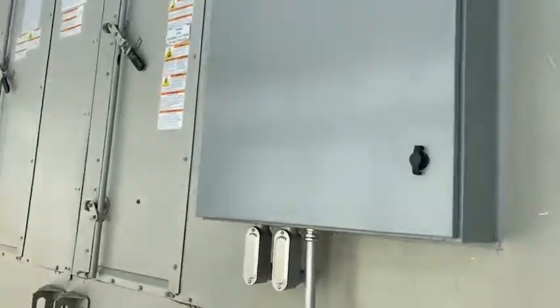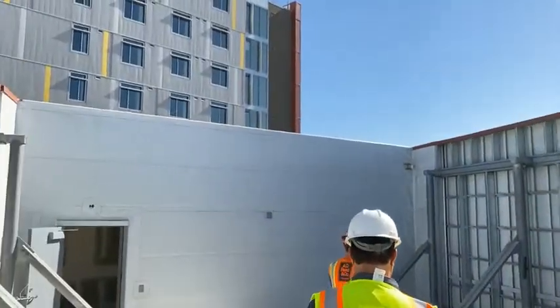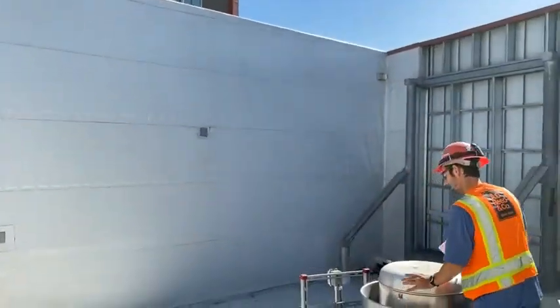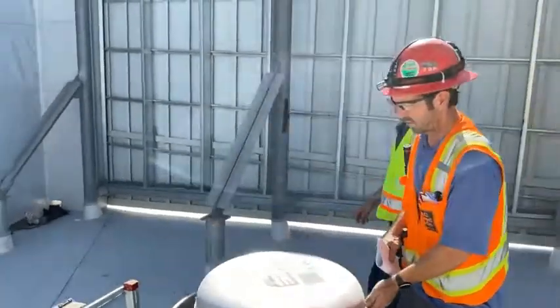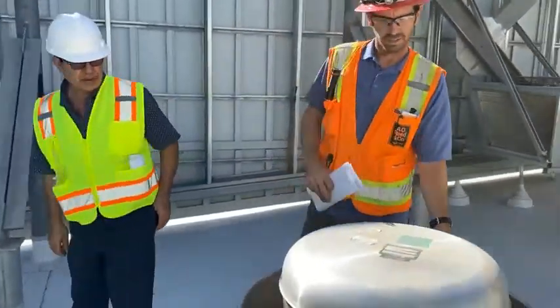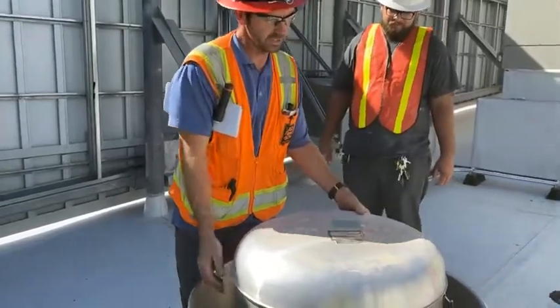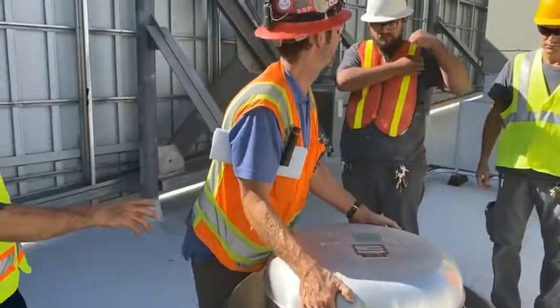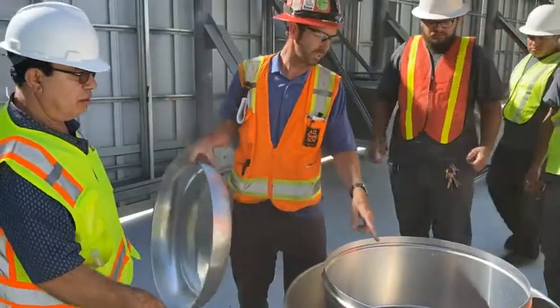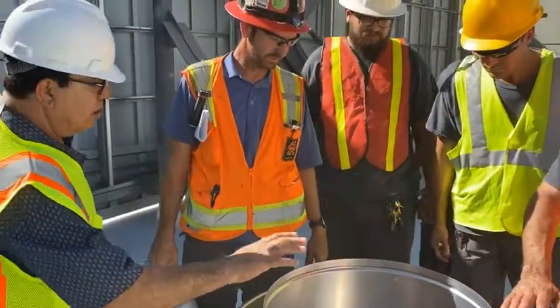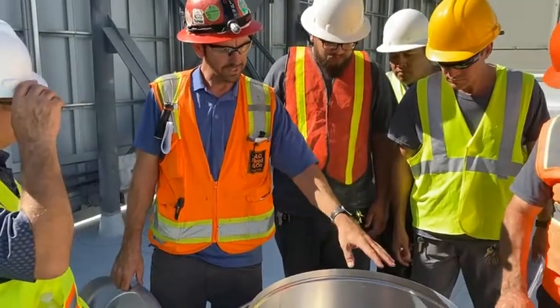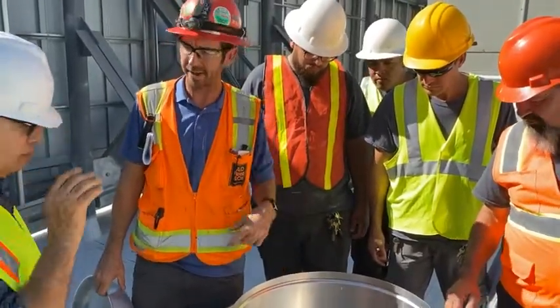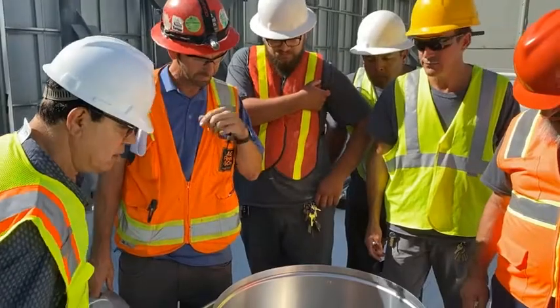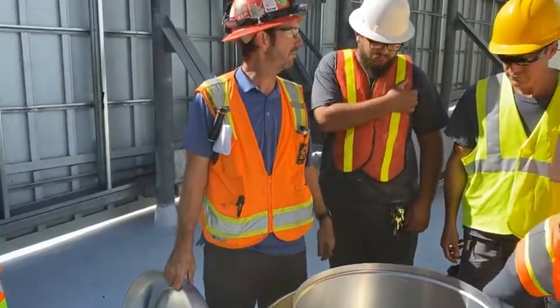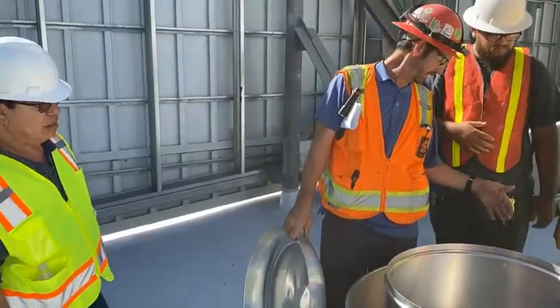And then lastly up here, we have EF3D. So this is one of the two different style units that's non-grease rated. It's a 120 volt ECM powered motor. There's no moving parts up in here unless you stuck your finger down there. It would be good practice to turn off power before you open the cover. Don't stick your hands down there.